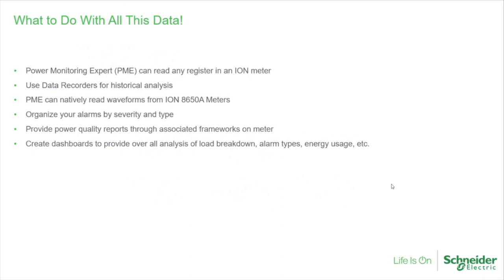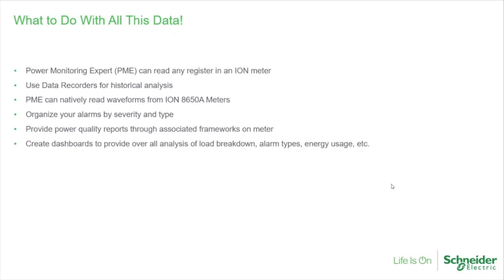PME can natively read the waveforms from the ION meters. And the ION meters store waveforms in their native ION protocol, as well as COMTRADE. If you download it as COMTRADE, then you can use something like PQView or PQ Diffractor, or some other applications, to view the COMTRADE file and analyze it. And with PME, you can also organize your alarms by severity and type. That's a new feature, I think introduced in PME 9.0, where you can categorize the alarms instead of just seeing a huge list of all the alarms. It helps filter them out for you.